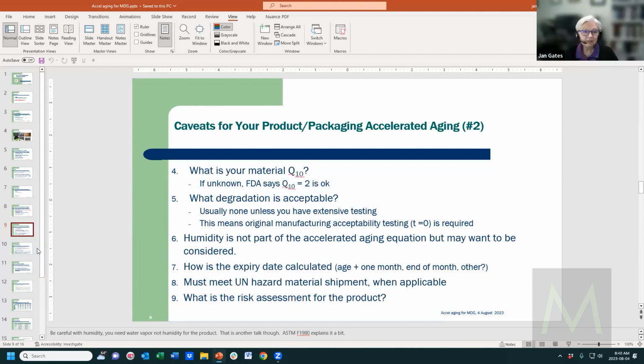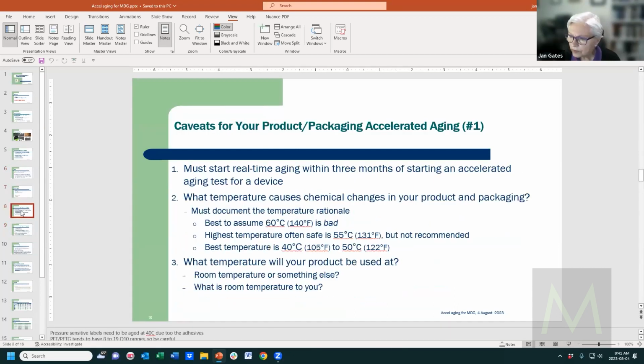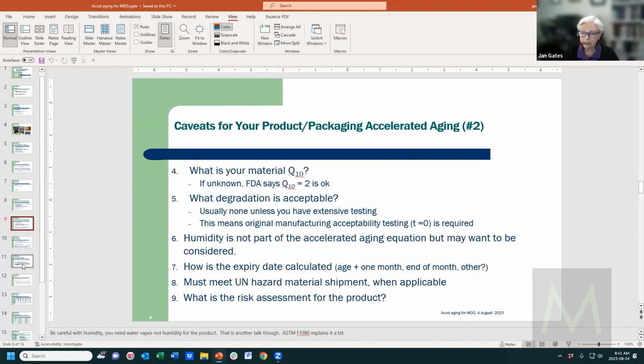So that's why you have a risk assessment too, to look at different pieces. And that's why you have to do your material research before you actually start doing your accelerated aging. But like I said, if you look at those temperatures, where I said it's best to assume 60 C is bad, don't use it. You might get away with 55 C, but 40 is usually the more conservative number to be using for your accelerated aging temperatures. And I had my caveats.